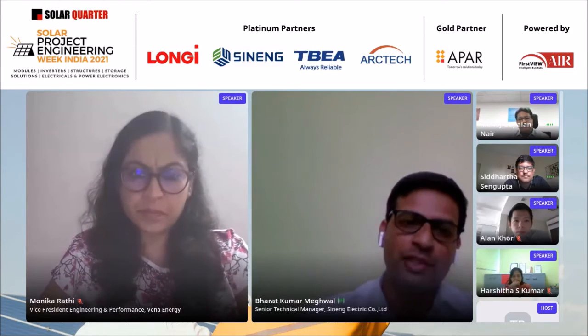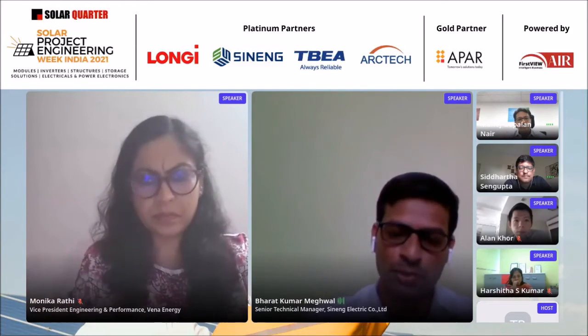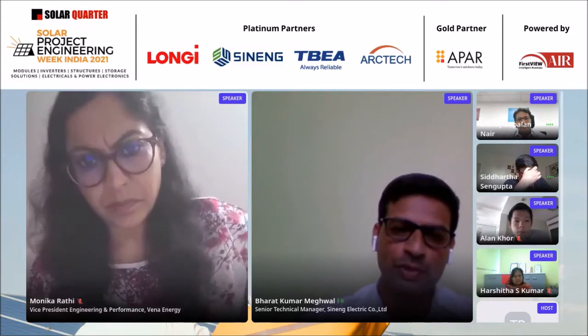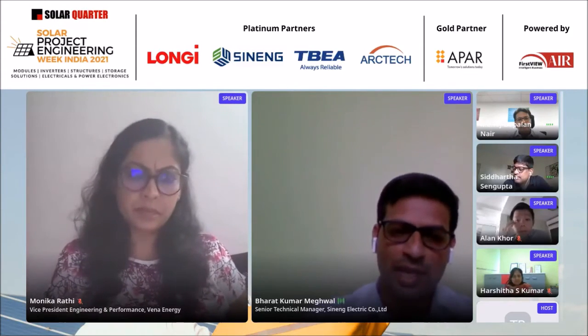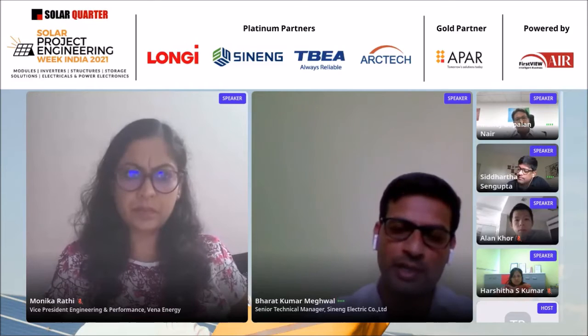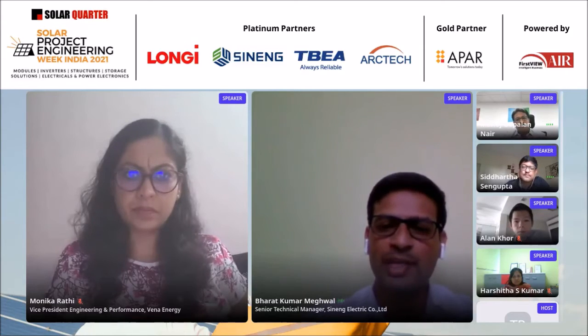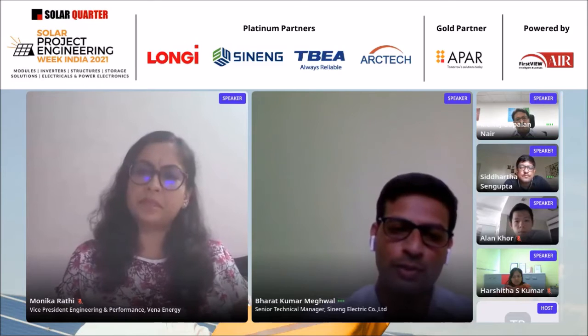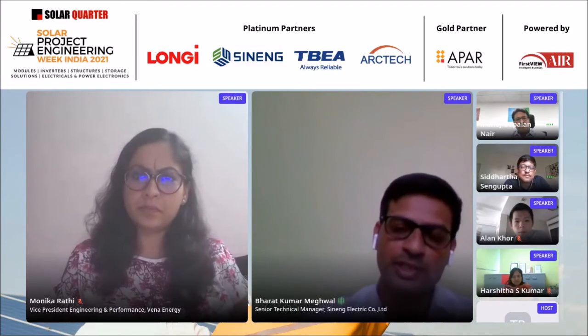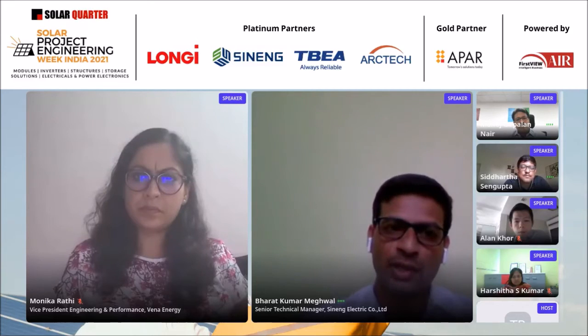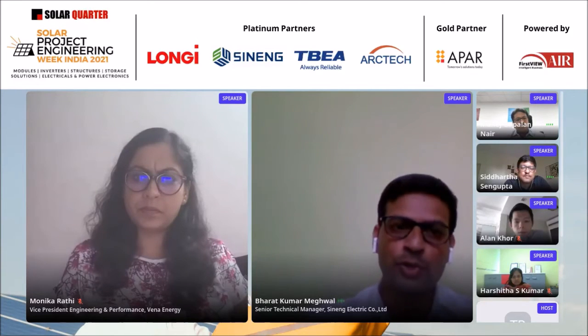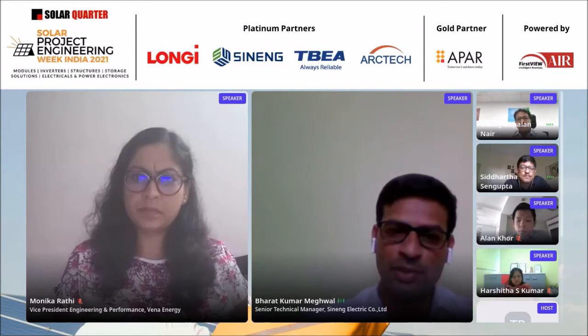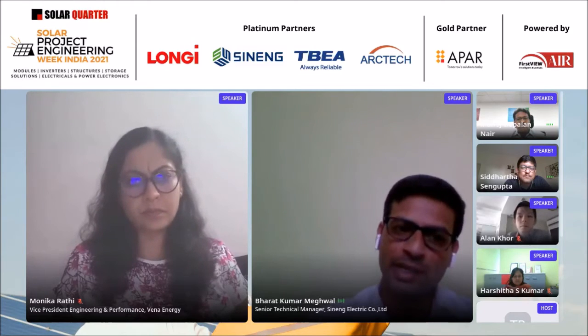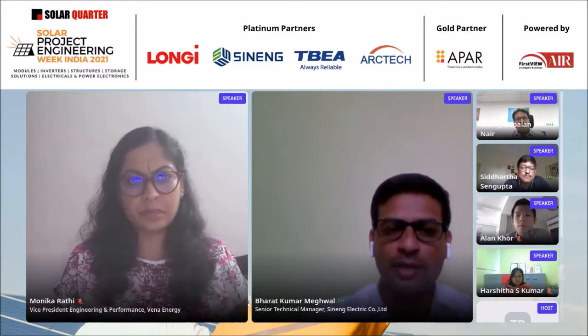First, I will talk about the bifacial module, taking it as an example. Bifacial module is a very recent technology for the Indian market. There are areas where we can have more generation from bifacial modules. For those particular areas, a distributed inverter is the best solution. The biggest problem we faced at the plant level was transmitting the DC power at the rear end. So if we use the distributed inverter solution, which is the latest technology, we can take most of the power from the bifacial module, utilize it, and convert it into an AC system.